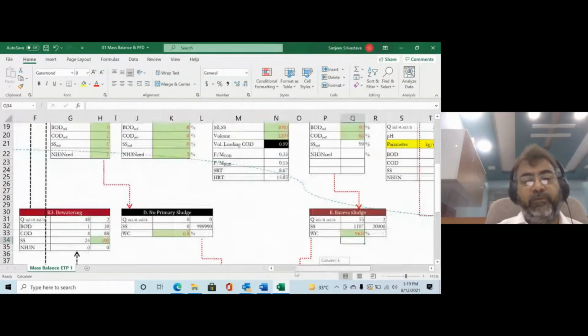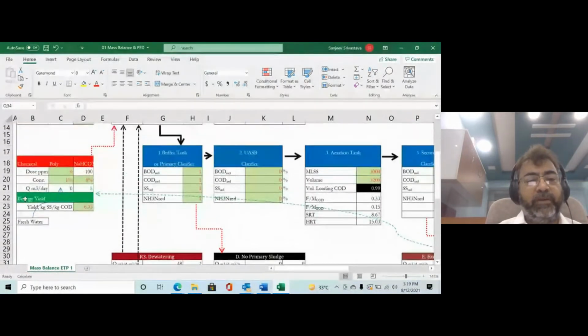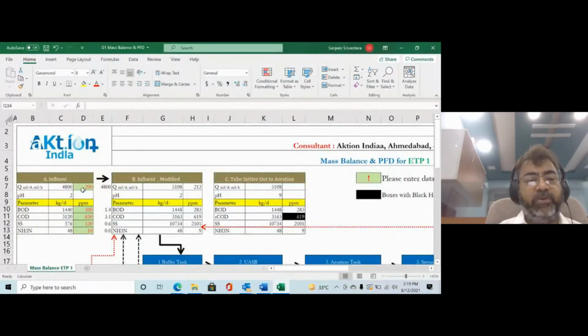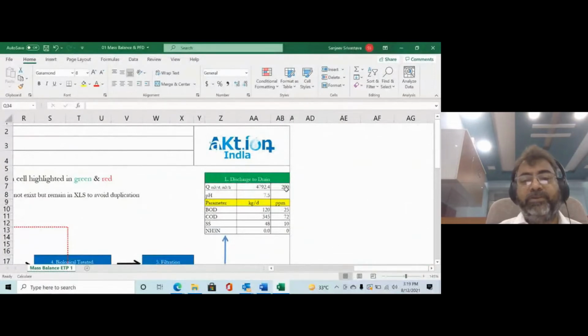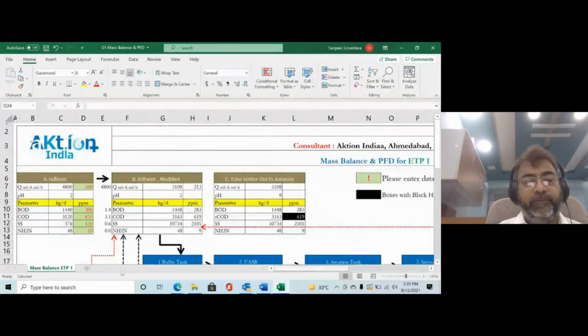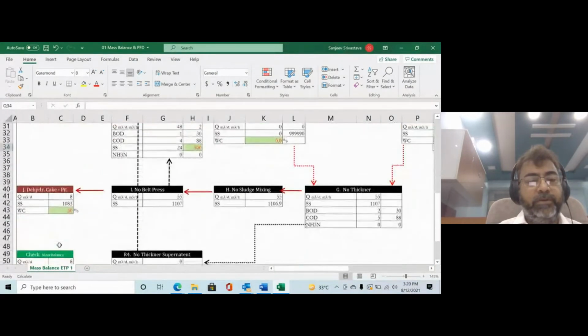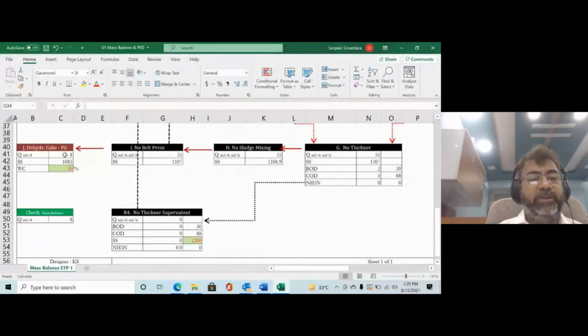And if you keep on understanding this, you will further find that if you are putting in 200 cubic meter of water, discharge to drain is 200, right? It is coming here. So water is going in the dehydrated cake as 8. Water coming in, check the mass balance, which is 8, not a problem. These two mass balances should match. 8 should be equal to 8, okay?